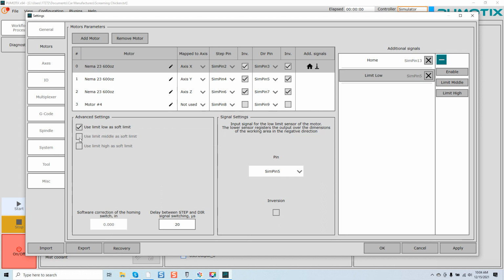I cannot set it for use limit middle as soft limit, or use limit high as soft limit, because these are only allocated to their specific signals. If I set limit middle, then I can use limit middle. If I set limit high, then I can use limit high. Very simple, straightforward, and logical.